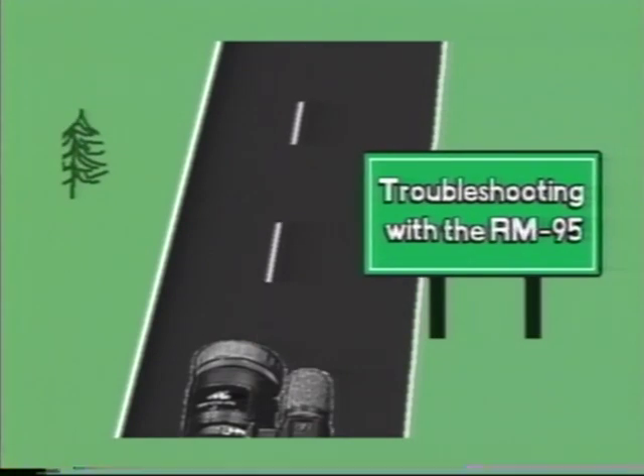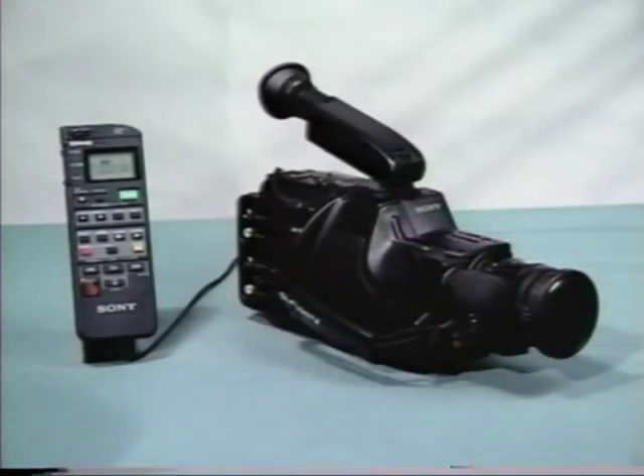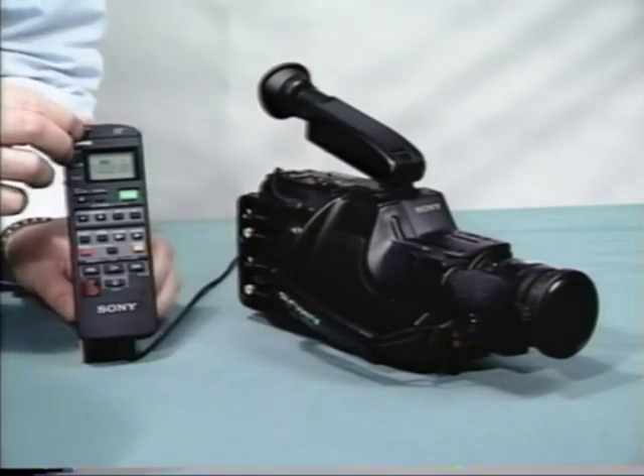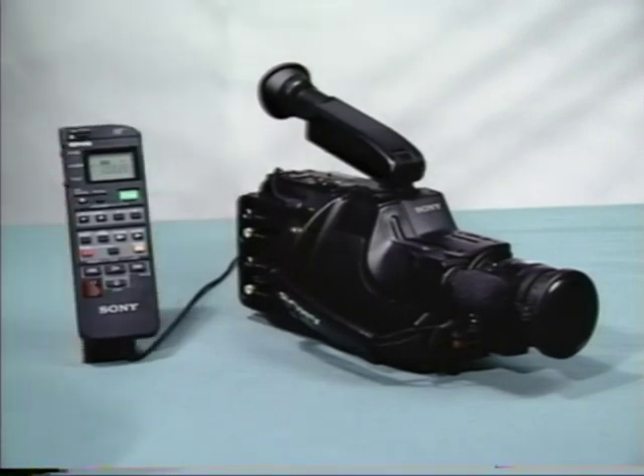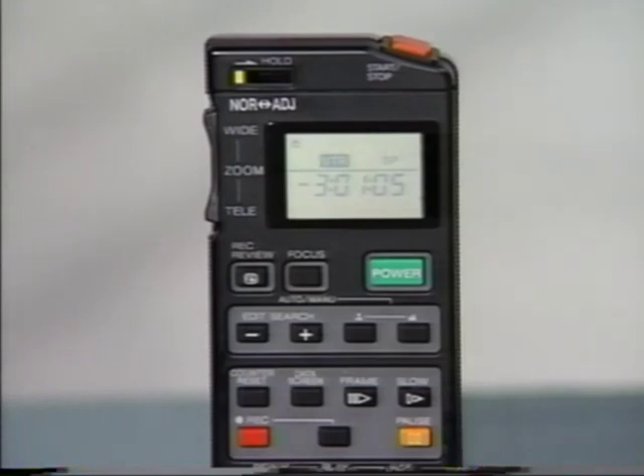The RM95 remote control can be used to quickly identify the cause of an emergency shutdown without actually opening the unit. Connect the RM95 to the remote control jack on the camcorder and place it in the service mode.